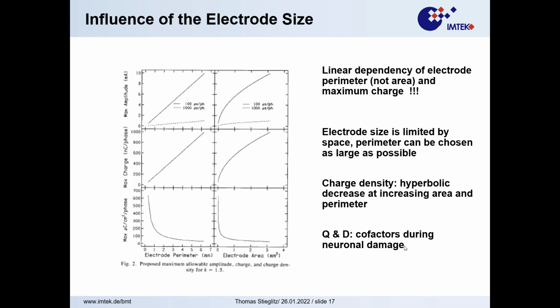If you would increase the pulse width, then it takes much longer for the charge to go somewhere, and then it takes the whole electrode area. But if the pulses are relatively short, many of the processes occur at the perimeter. And therefore, it makes a kind of sense that the perimeter has a linear relationship to the maximum charge that I can deliver, and not the area. That is an important issue, and a lot of people played around with the shape of electrodes. I mean, if they are handmade and you would take a pair of scissors and you have to cut something, or you need to stamp them out, you would probably stick to disks.